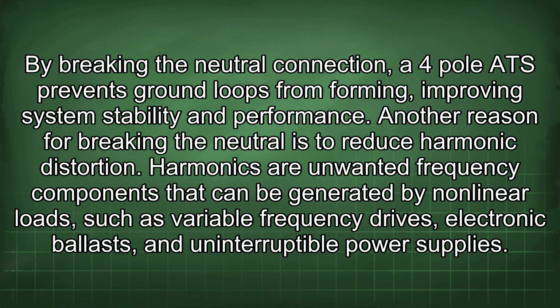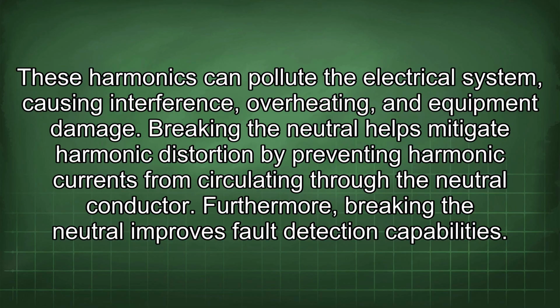Another reason for breaking the neutral is to reduce harmonic distortion. Harmonics are unwanted frequency components that can be generated by nonlinear loads, such as variable frequency drives, electronic ballasts, and uninterruptible power supplies. These harmonics can pollute the electrical system, causing interference, overheating, and equipment damage. Breaking the neutral helps mitigate harmonic distortion by preventing harmonic currents from circulating through the neutral conductor.